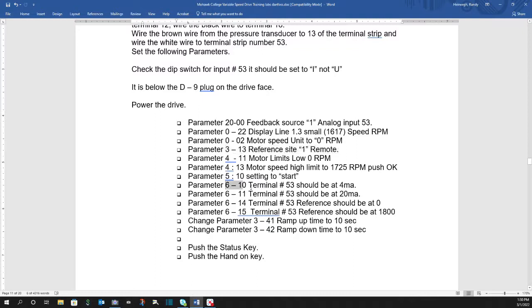Maybe not so straightforward. You have to go into 610 and tell it the minimum and maximum when it needs to move. And then if you keep scrolling through parameter 6, it then says, hey, what do you want to do for the RPM? So if you had a motor that you didn't want to start at 0, you want it to start at, say, 600 RPM, which, again, you have to be cautious of sleeve-bearing motors versus ball-bearing motors. Sleeve-bearing motors have to be brought to their full RPM first to get the oil out of the babbitt onto the bearing. So that's why traditionally more and more motors are ball-bearing, which don't care about the minimum and maximum. And so that should probably be changed, reference to 1800. It should be changed to 1725 as well, which doesn't really matter to me.